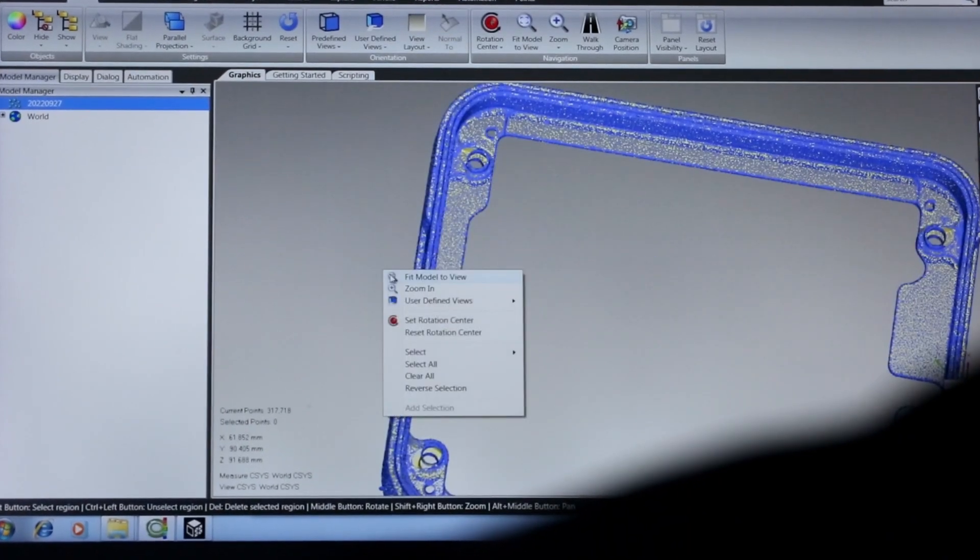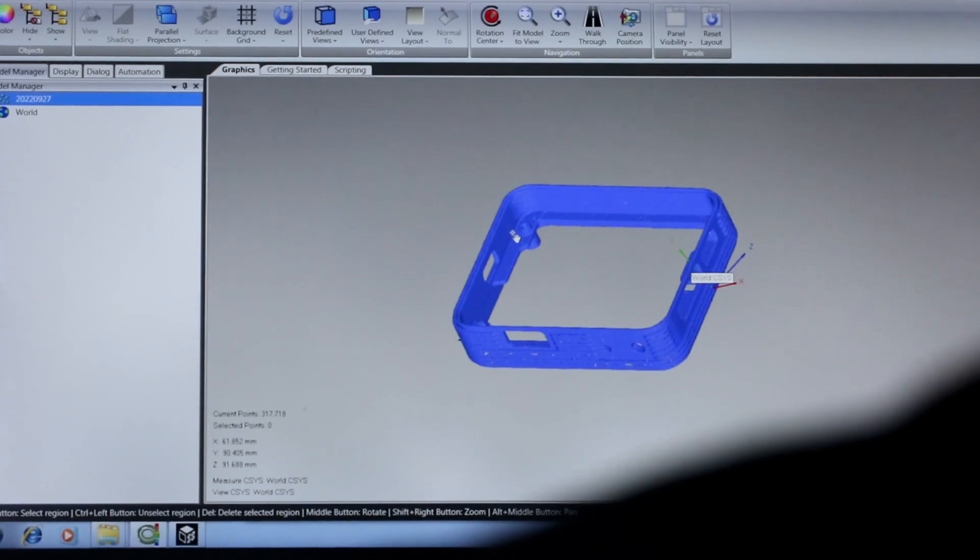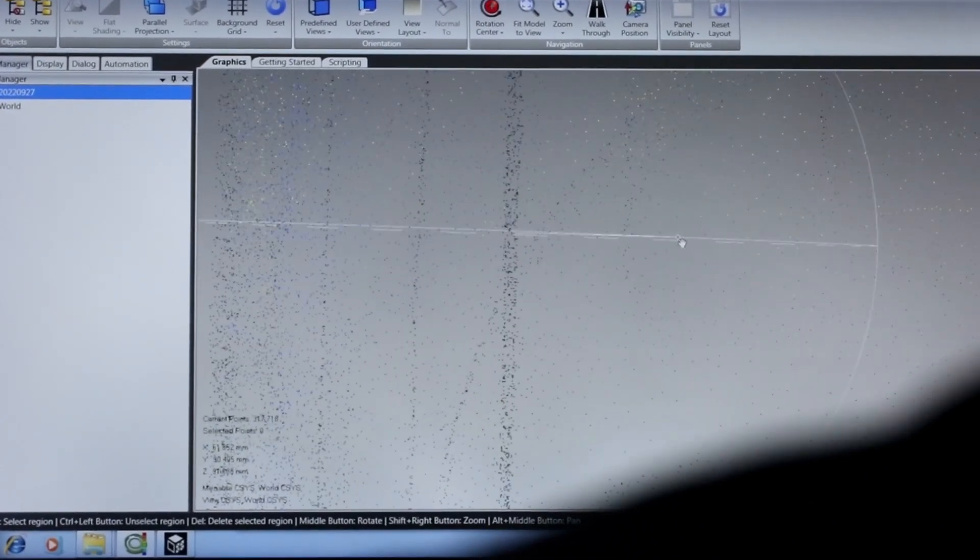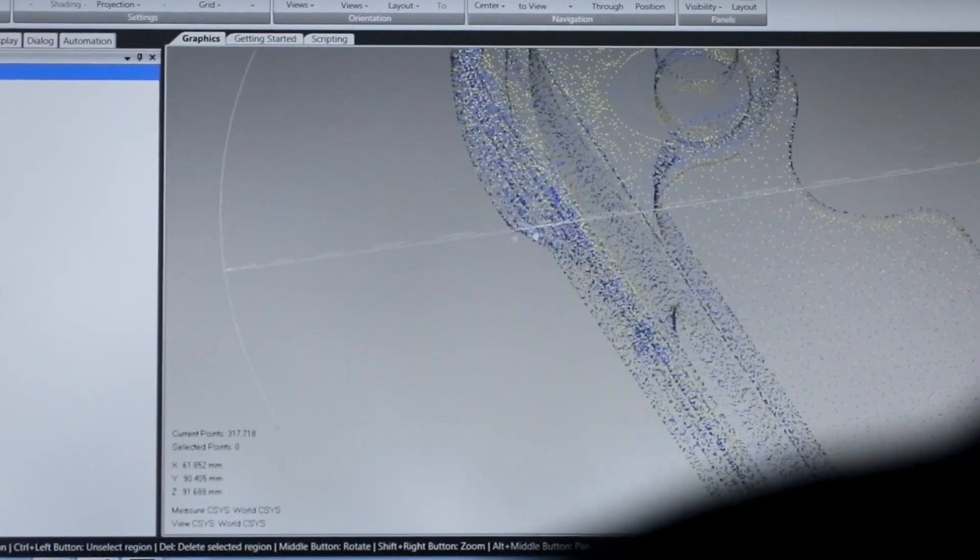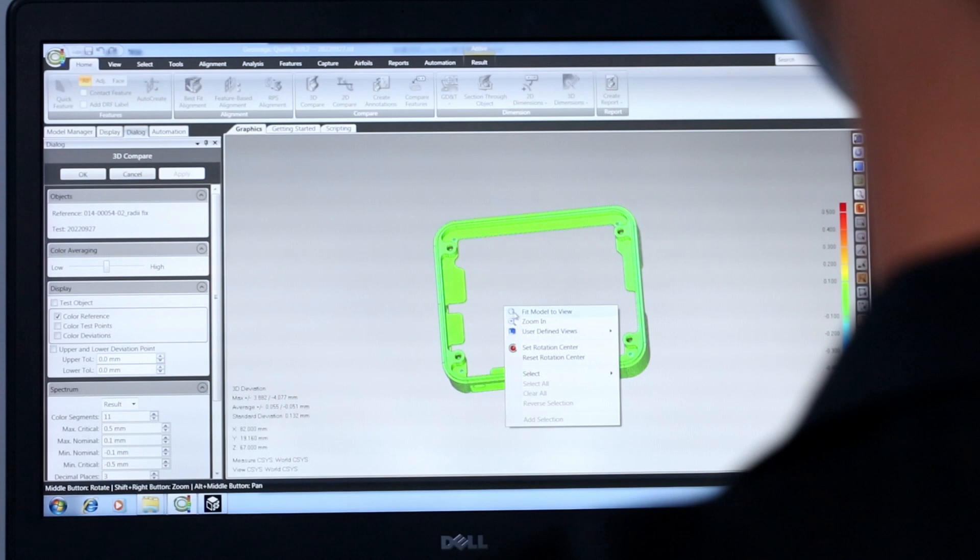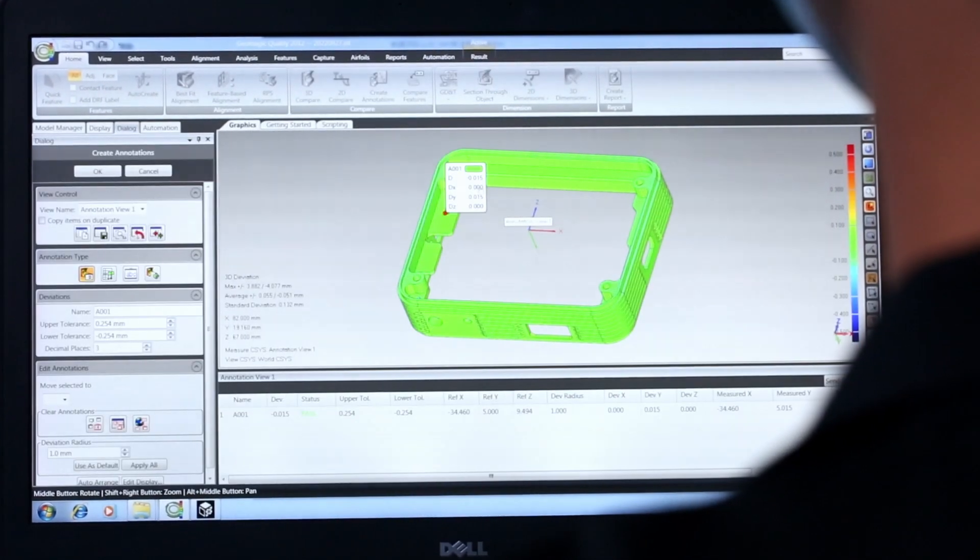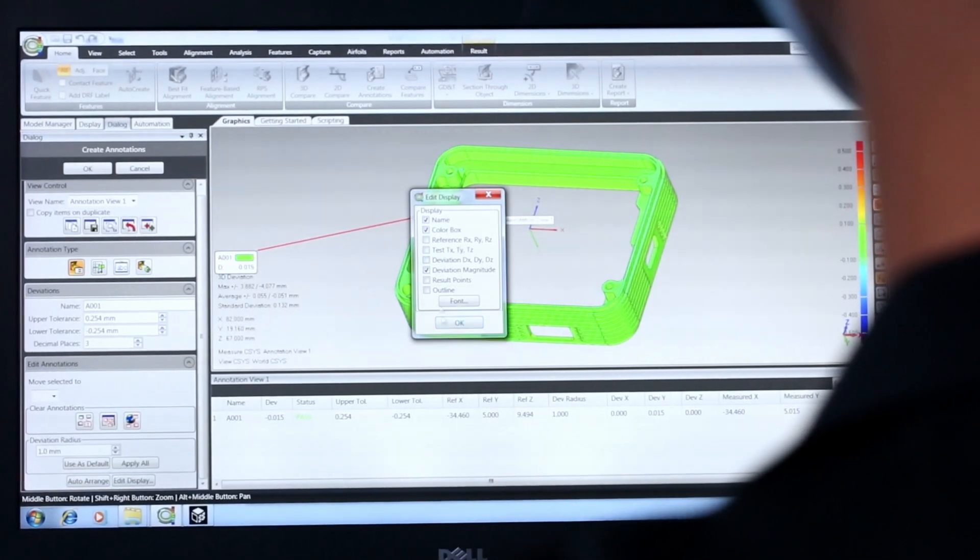These points are fed into specialized software, which creates a point cloud, and from this cloud, a complete 3D CAD model of the part can be easily constructed. We typically take the model generated from the Zeiss and compare it to the CAD file supplied by the customer. The model can be rotated until it achieves a best fit with the reference, and from there we can identify any discrepancies.